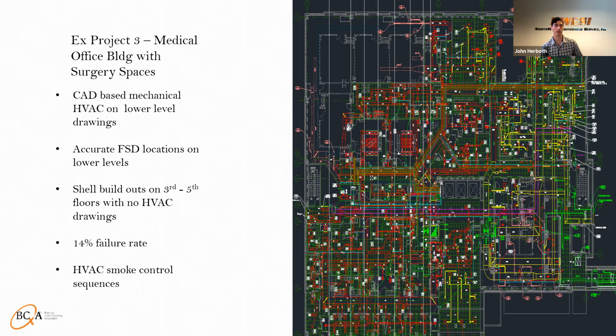It's another mixed use building. There's more HVAC smoke control sequences, but we had a 14% failure rate on a building that had some critical ORs in it, and that is a problem. It's normal to see failure rates 10% and lower that I've experienced, but once you get to 15, 20, 25, that's just really high.